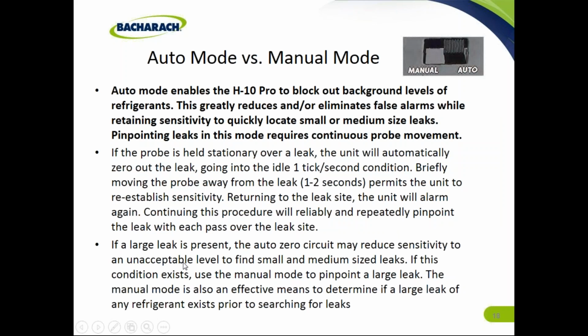So once again, they're going to go over the auto mode versus manual mode. The auto mode enables the H10 Pro to block out background levels of refrigerant. This greatly reduces and eliminates false alarms while retaining sensitivity to quickly locate small and medium-sized leaks. Pinpointing leaks in this mode requires continuous probe movement.